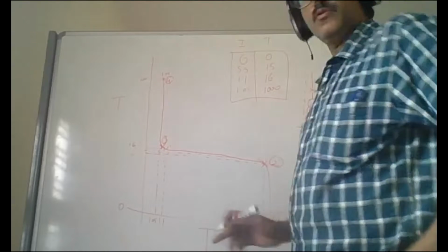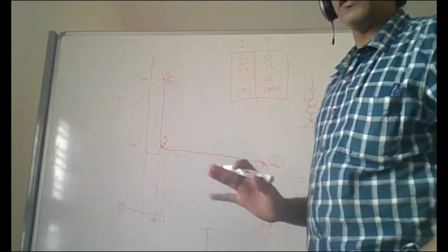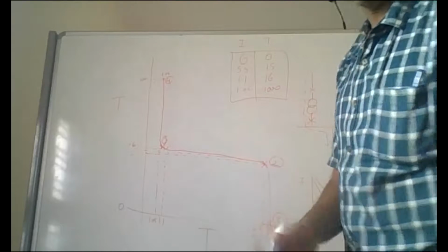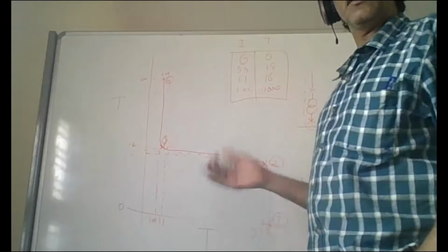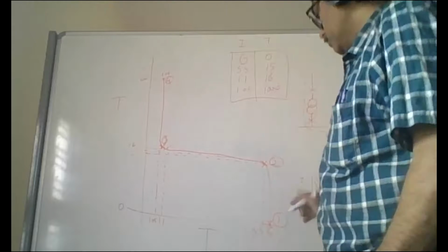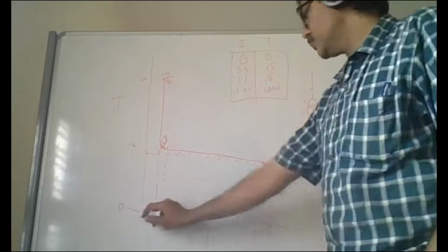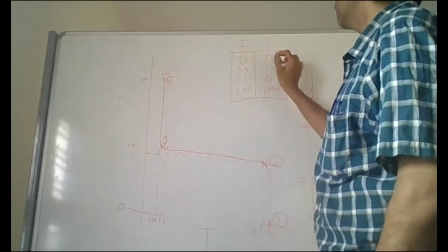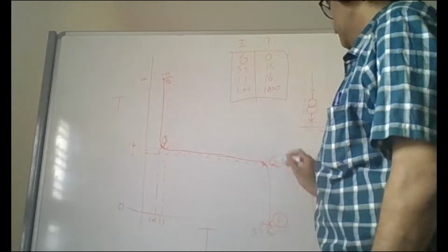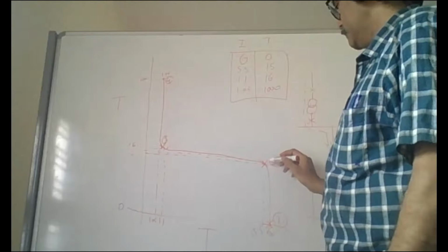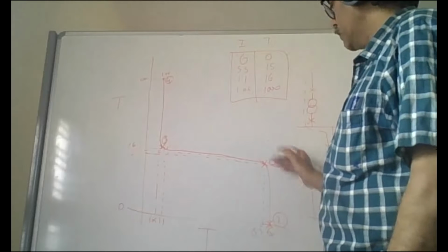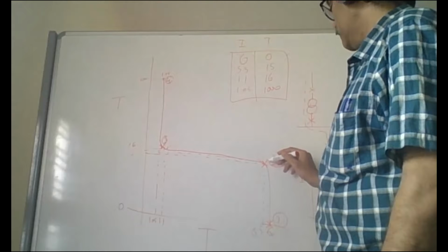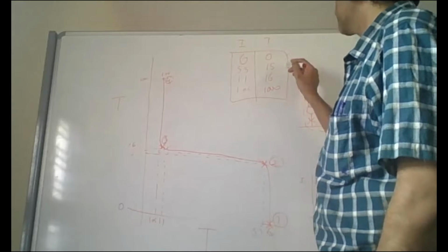Or you get the curve. Let's assume I already have a curve, and now I'm converting that curve to Excel data points. At time t equal to 0, it is 6 times current. So t equal to 0, 6. This is the first point. The next point is where the curve is bending. I will assume at 5.5 current the curve bends, and that takes 15 seconds.